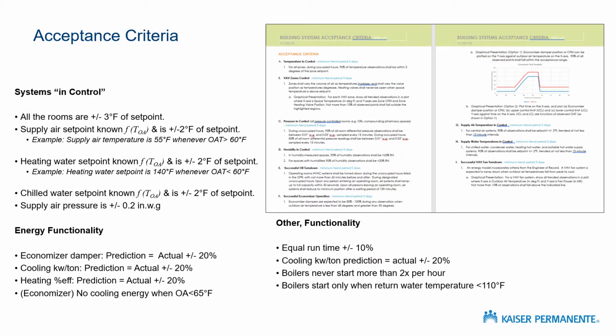Before I do that, I'll show you what we mean by working to the design intent. We've actually developed in the last few years these acceptance criteria, and we have the engineers put them on the plans or on the specifications. So we try to be very, very clear, numerically clear about what we expect to see during the trending period. We want to see the rooms in control. We want to see economizers work. We want to see fans and chillers and boilers and pumps ramp up and ramp down as the weather ramps up and ramps down. And so that's what I'm going to show in these next few slides. It's an example from a project that did their trending period and has the results to show.